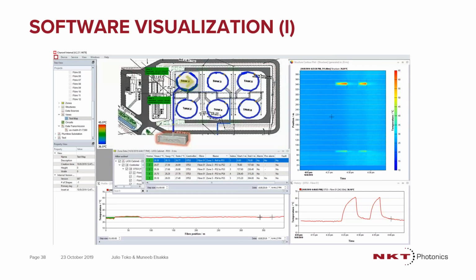There's other things that you can do from a visualization point of view. We talked about tank farms. You can actually bring up more, except for just activating and being integrated to the fire panel. We can give you data directly to work with the other vendors' software applications, let's say, or visualization system. But our system or any other system from other vendors does come with a software visualization most of the time, where you can lay out the area and show different tanks and different rates of rise that have been happening. And you can actually base your alarm parameter on what you've seen in the past.